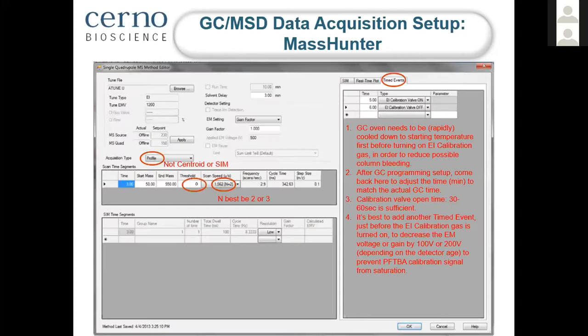Now, nowadays, most of the new GCMSD comes with a MassHunter data acquisition, which pretty much has only a single page where you need to make all the setup. So the terminology for acquisition type has been changed to profile instead of centroid or SIM. And then the threshold you can change right here on the same page to zero. The scan speed, we want to keep it in the medium range, typically 2 or 3 or 4. And the timed events is very similar to ChemStation with similar notes and explanations here.